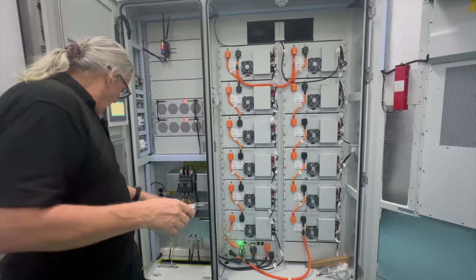So look at the difference, understand it. From a wiring point of view, all you've got here is your three-phase connections, three-phase neutral, wiring to it. You have two configurations: if you're wiring in certain countries like the Philippines, you may be on a Delta grid, and you haven't got a neutral. For the UK or South Africa, you're on a star grid, so you have a neutral. It's as simple as that.